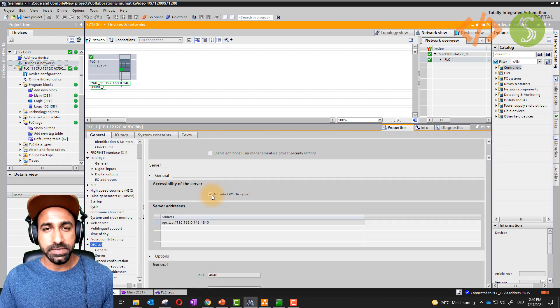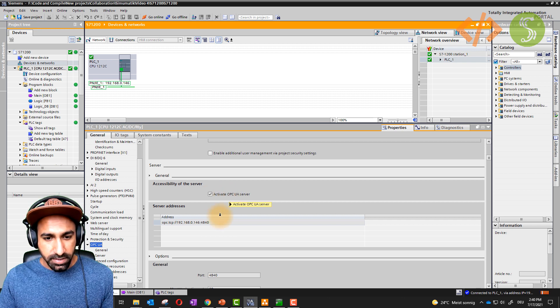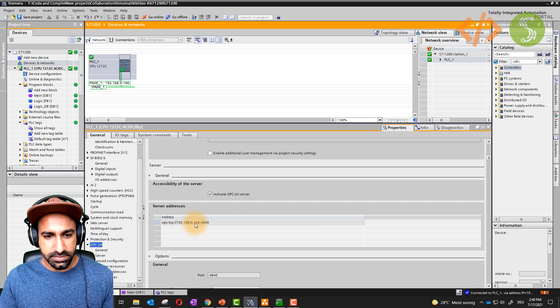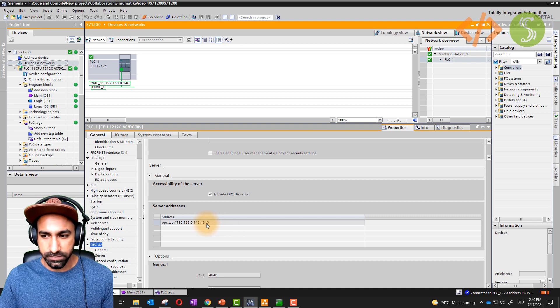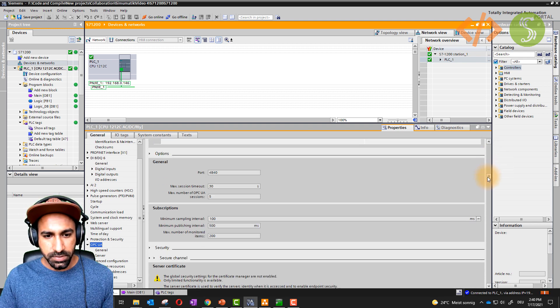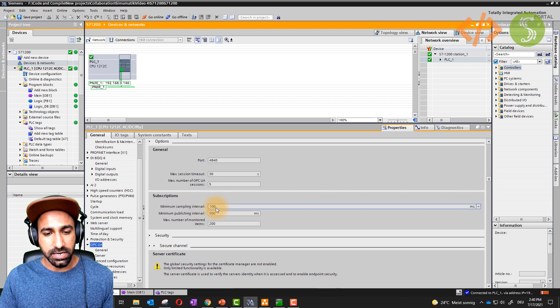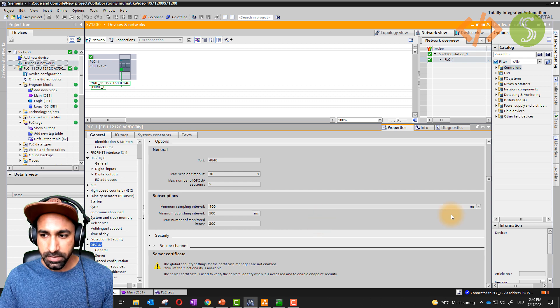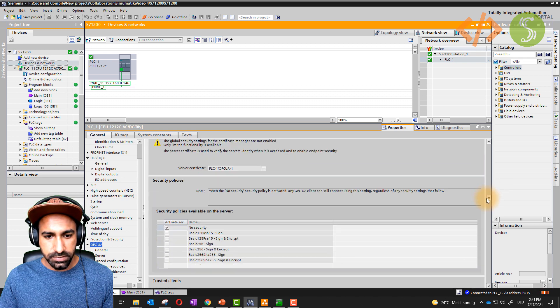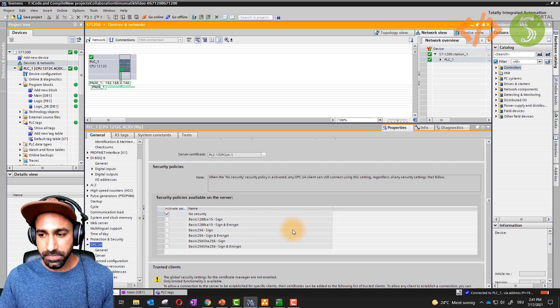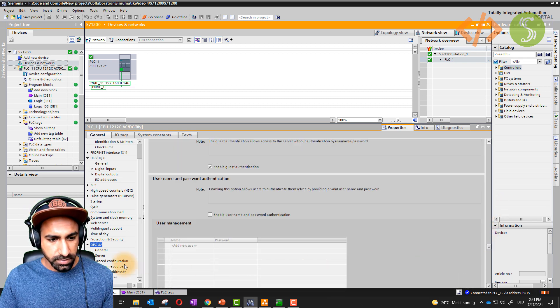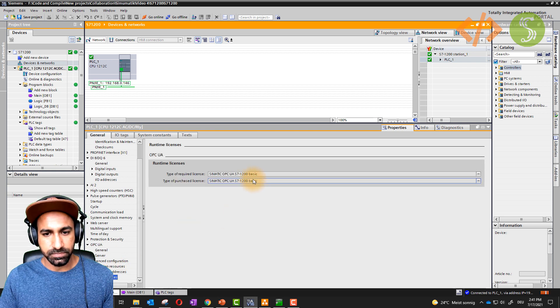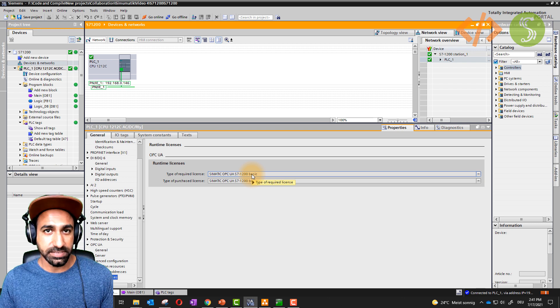Next, go down to OPC UA settings. Activate your OPC UA server — that's the first step. Once you activate that, you'll automatically get a port number. The URL is basically the IP address of your PLC plus the OPC UA port, which is by default 4840. Go down and set the minimum sampling interval to 100 milliseconds. I have set the security to no security in this example. Also check that the runtime license is set to basic.